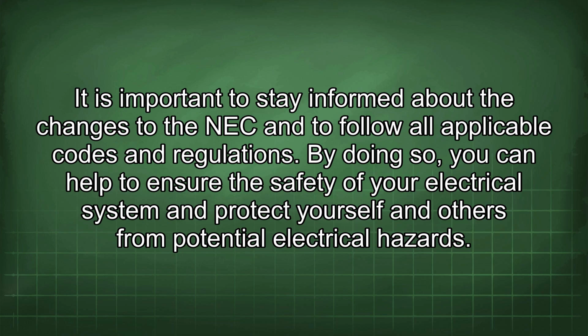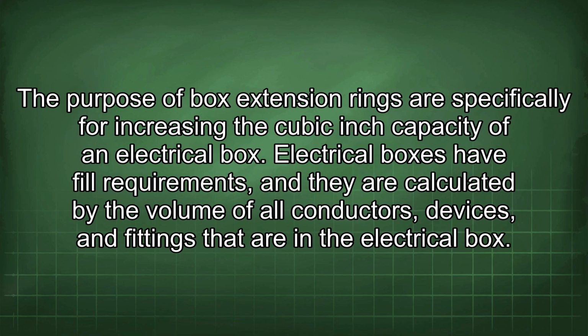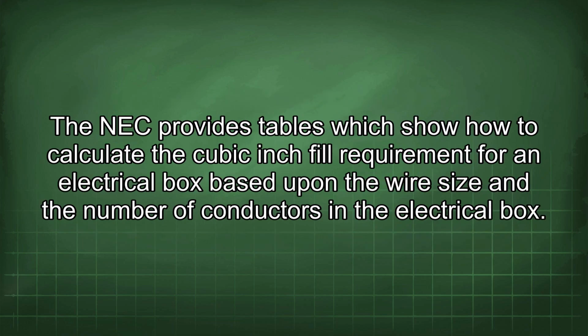The purpose of box extension rings is specifically for increasing the cubic inch capacity of an electrical box. Electrical boxes have fill requirements, and they are calculated by the volume of all conductors, devices, and fittings that are in the electrical box. The NEC provides tables which show how to calculate the cubic inch fill requirement for an electrical box based upon the wire size and the number of conductors in the electrical box.